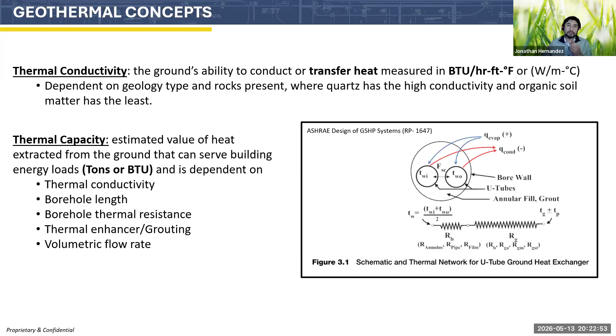And that is why a thermal response test or a thermal conductivity test is performed to finalize your design or finalize your bore field. It won't make a huge difference. Typically, it just reconfirms what's already known. But in an off chance, it just means wells may get 10 feet deeper. It doesn't affect materially your cost or your scheduling.